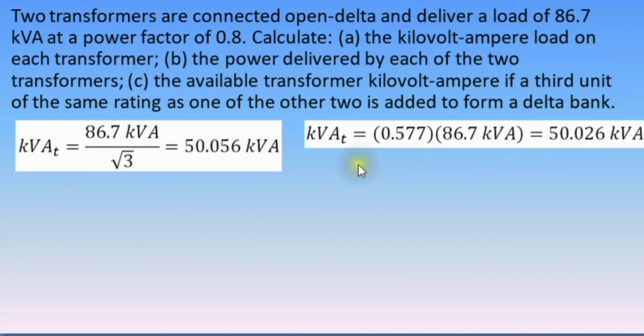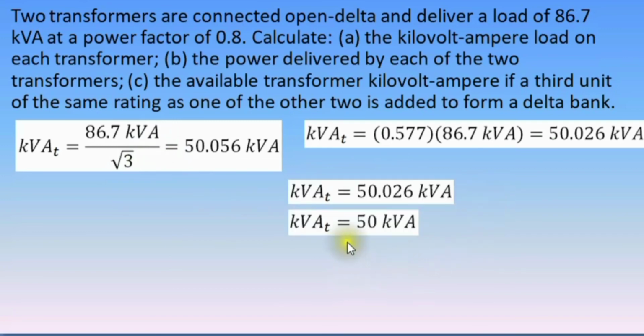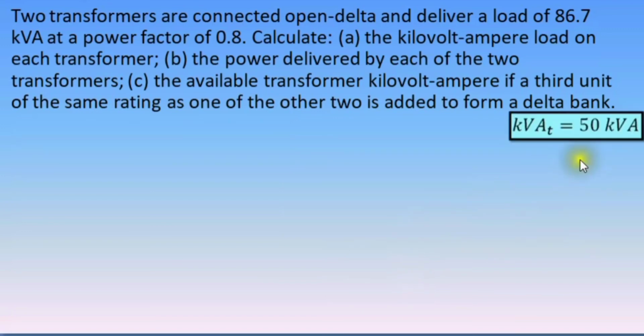Or another way is to multiply 0.577 to the total kVA delivered to the load, that is 0.577 times 86.7 kVA, the answer is 50.026 kVA, since 1 over square root of 3 is equal to 0.577. But of course, we can round off our answer to 50 kVA. So the kilovolt ampere load on each transformer is 50 kVA.